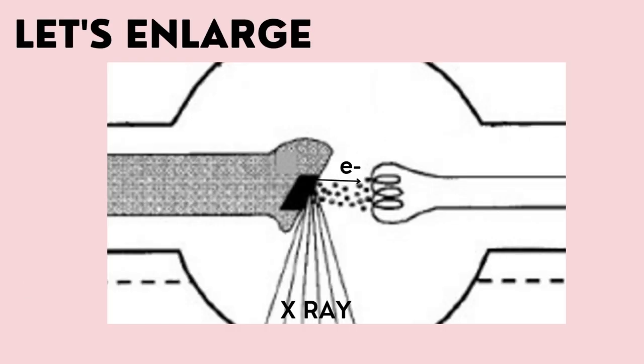When the tungsten filament is heated by the current flowing through it, the increased energy enables the electrons to be released from the filament. The electrons are attracted towards the positively charged anode and hit the tungsten target with maximum energy. As the electrons bombard the target, they interact via Bremsstrahlung and characteristic interaction, which results in the energy being converted into heat and x-ray photons. The x-ray photons are released in a beam out of the window of the tube, forming the x-ray image production.